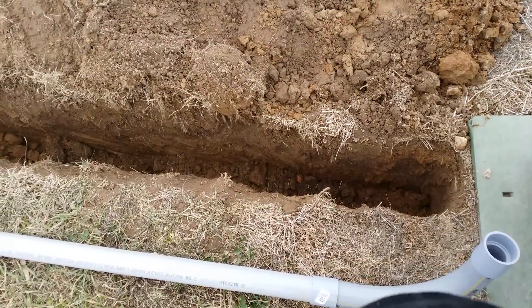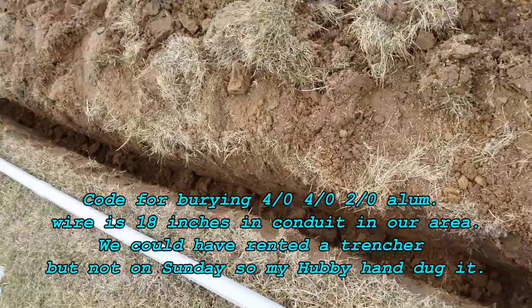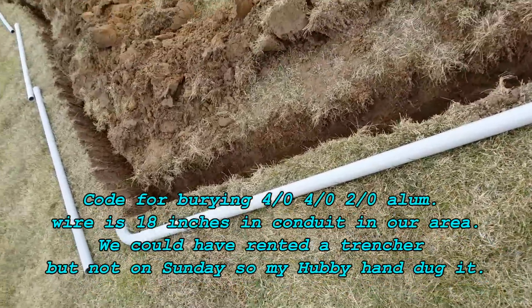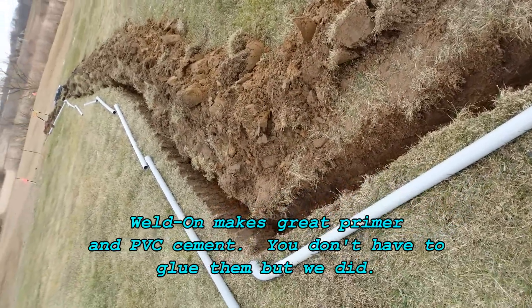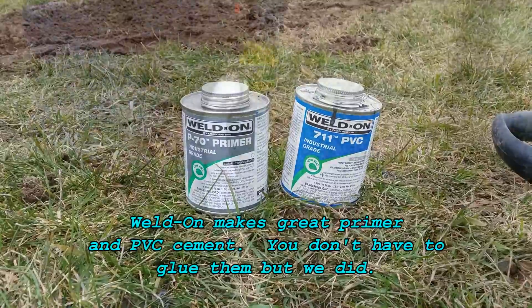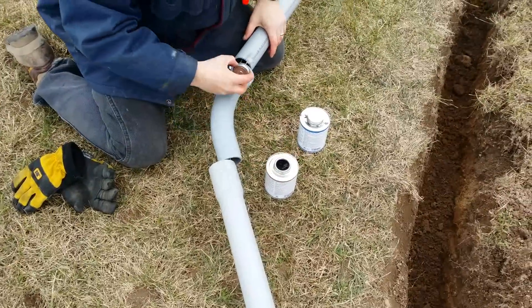Now you can see we've got the trench here and our conduit laid out. The trench is 18 inches deep — that's code here in our area. You have to bury your electrical cable 18 inches in conduit. We're also going to cement ours together because we feel it'll stay better when the ground shifts and freezes. We used a Weld-On product and we've been really happy with that.